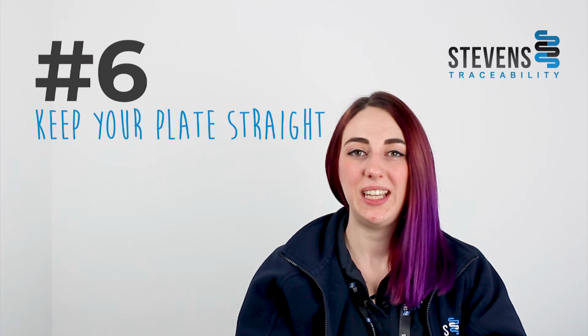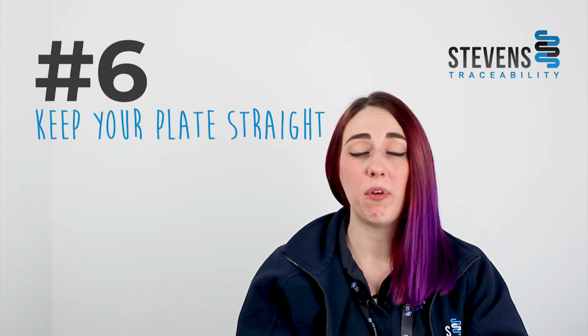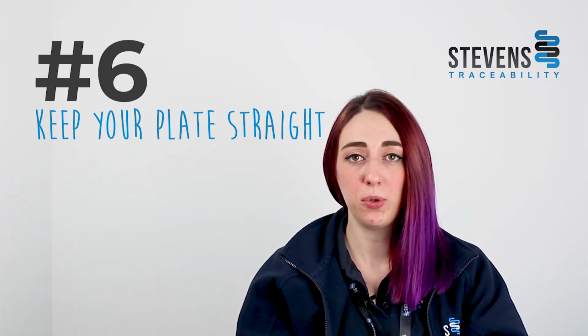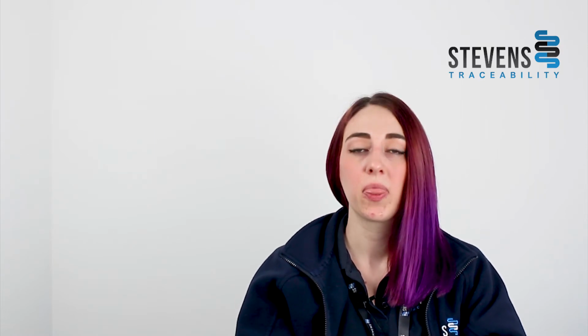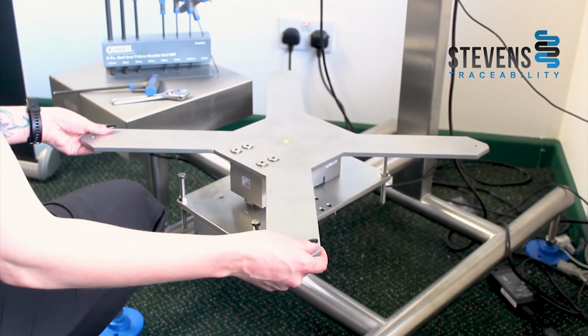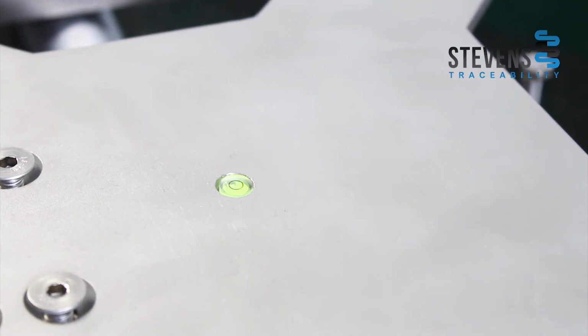Tip number 6, keeping your plate straight. Whether you have a bench scale or a platform, it is important to make sure the plates that sit above the load cell are straight or in good condition. If you have a bench scale, to check this is to take the plate off and lift it upside down to ensure all of the frame underneath is straight and all the bolts are where they should be. If there is any dent or damage to the plates, this could cause uneven weighing, which could cause you major weighing issues. The same is for a platform.